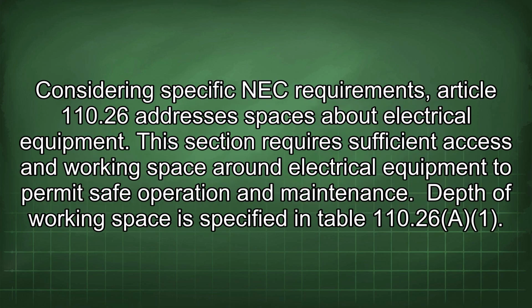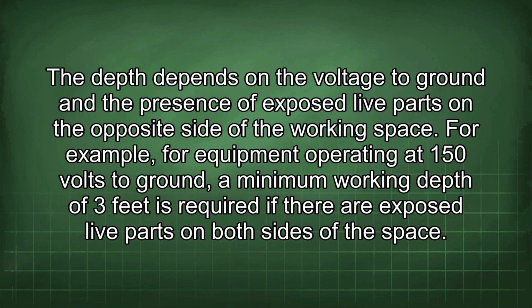Considering specific NEC requirements, Article 110.26 addresses spaces about electrical equipment. This section requires sufficient access and working space around electrical equipment to permit safe operation and maintenance. Depth of working space is specified in Table 110.26(A). The depth depends on the voltage to ground and the presence of exposed live parts on the opposite side of the working space. For example, for equipment operating at 150 volts to ground, a minimum working depth of 3 feet is required if there are exposed live parts on both sides of the space.